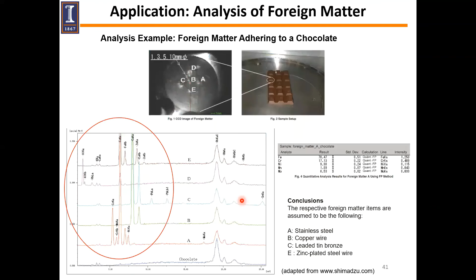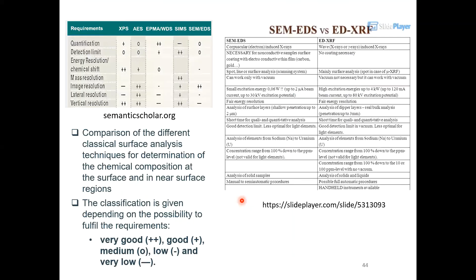Okay. How about the comparison between running the instrument under helium or vacuum? I think you showed data comparing air and helium, but do you have anything comparing vacuum versus helium? I don't have that graph, but with helium, you can measure up to the sodium atom. And if you want to go beyond sodium, you have to use a vacuum system. Because beyond sodium, the energy is very low, and even though we use helium, we don't get enough fluorescence energy to be detected by the detector. So that's one of the limitations of helium use in XRF.